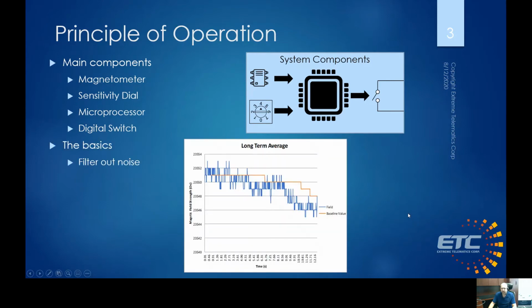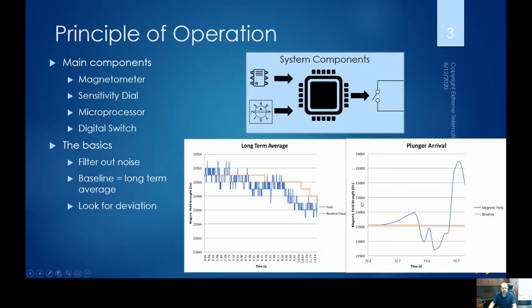So the basics are, we take those magnetometer readings, we filter out any really high frequency noise, as you can see here, and then we try to come up with a long-term average to indicate what no plunger looks like. Then we look for a deviation. So you can see here the red line that was used to get rid of the noise is the baseline. You can see here zoomed out, we see much larger changes when a plunger comes in, and then we can close the switch. We determine that there's been an arrival of the plunger.